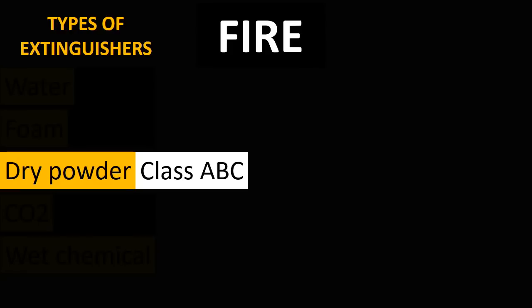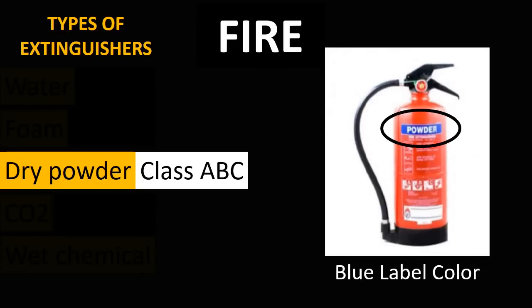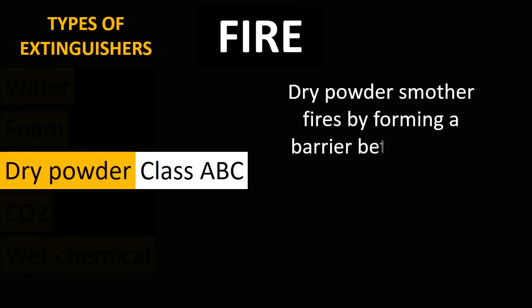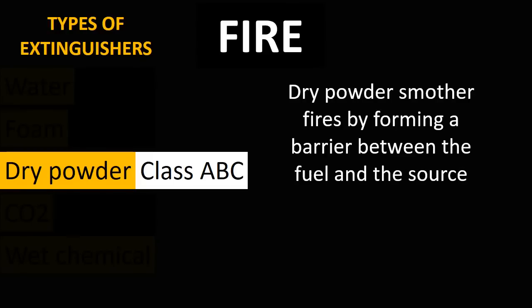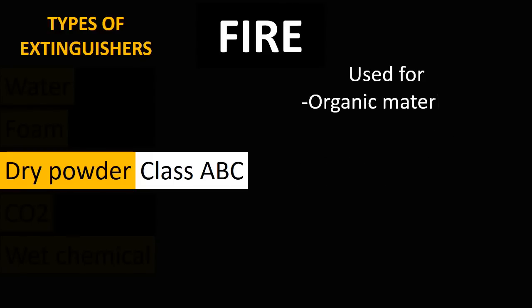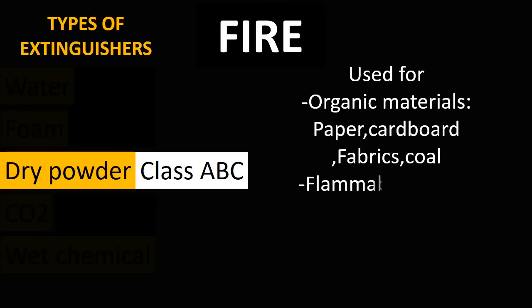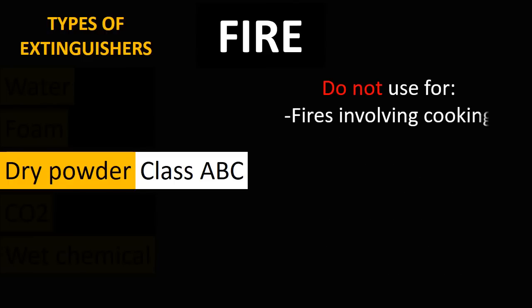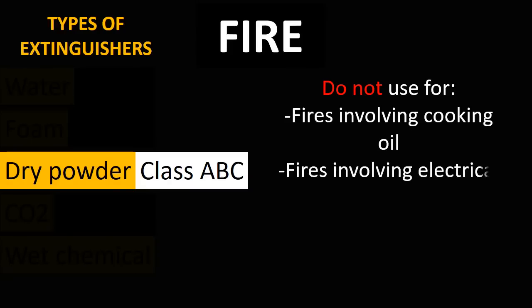The third type of fire extinguisher is dry powder. Dry powder type fire extinguishers can be used in Class A, Class B, or Class C fires and they have a blue label color. Dry powder smothers fires by forming a barrier between the fuel and the source. Dry powder fire extinguishers are used for organic materials such as paper, cardboard, fabrics, and coal; flammable liquids such as paint and petrol; and flammable gases such as LPG and acetylene.